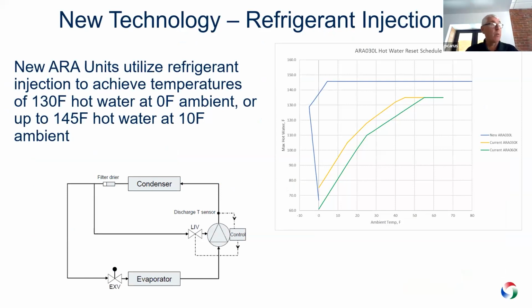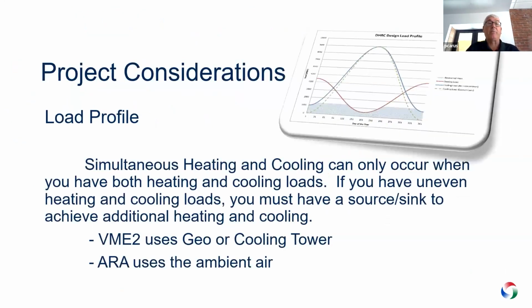At higher temperatures, we can do up to 145 degrees, about 10 degrees Fahrenheit. You can do about 145 with that particular machine. Critically important that you understand your load as well as you possibly can, because that will dictate size of machines, programming logic, when you're in heating, when you're in cooling, and how much simultaneous capability that you have. There's another version of this called a VME2 that's a water-cooled version. So take the ARA version and assume that you're doing water-cooled and using a valve structure that can manage the diversion process for you in a water-cooled heat recovery type of machine.